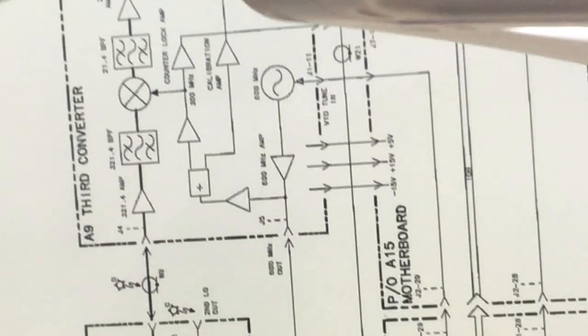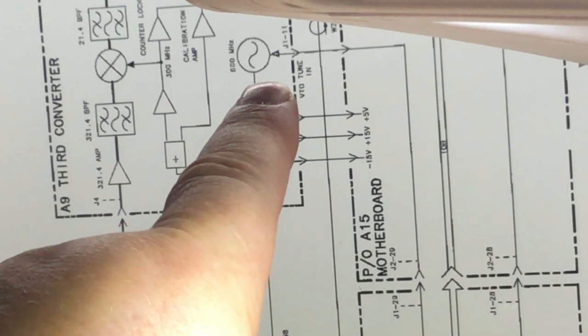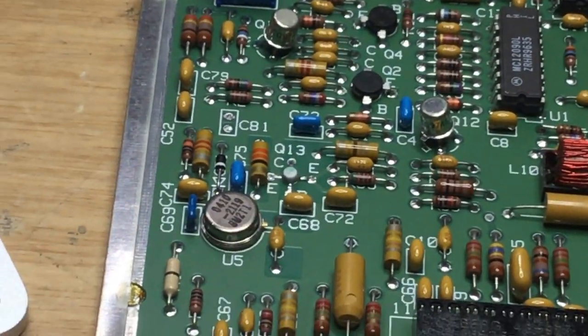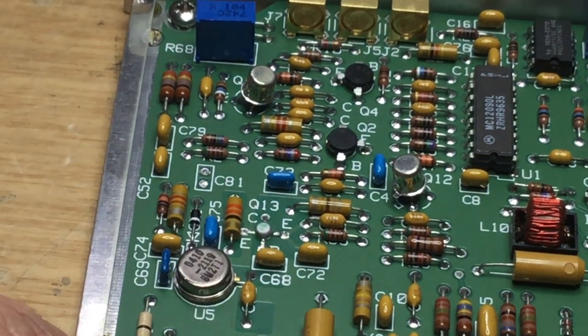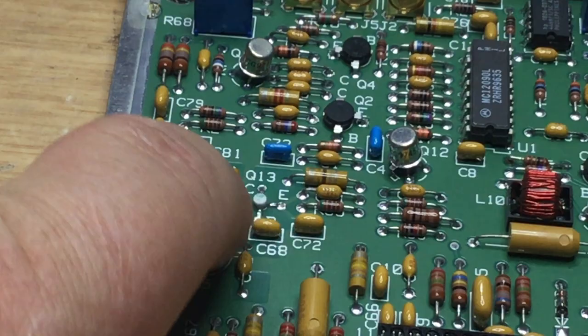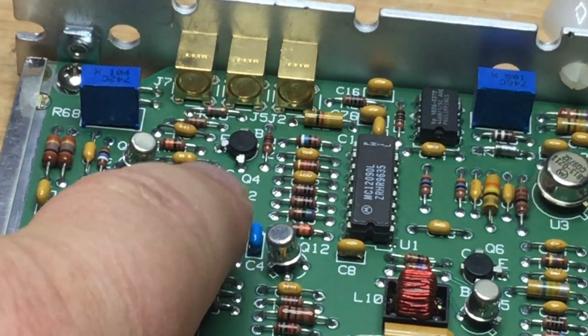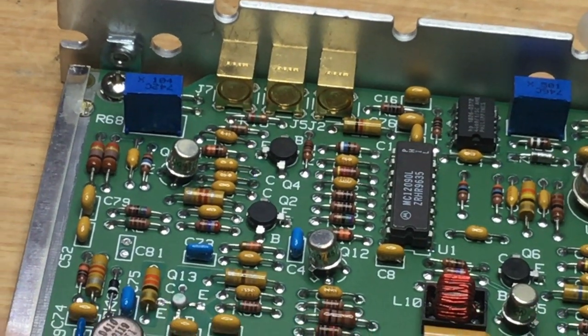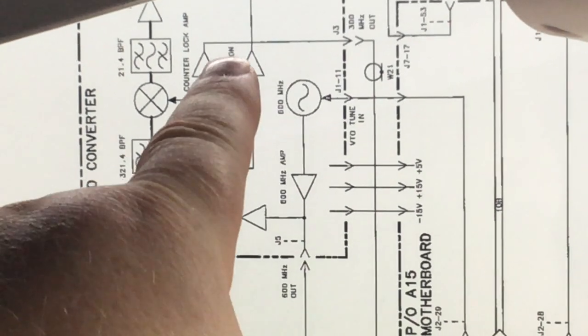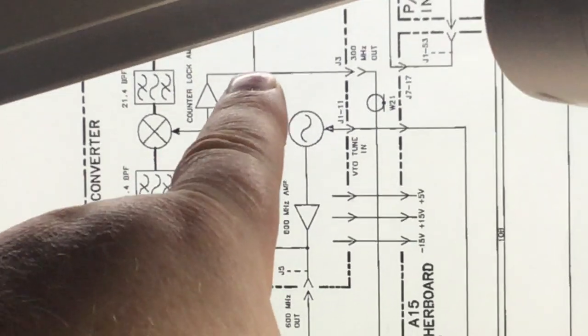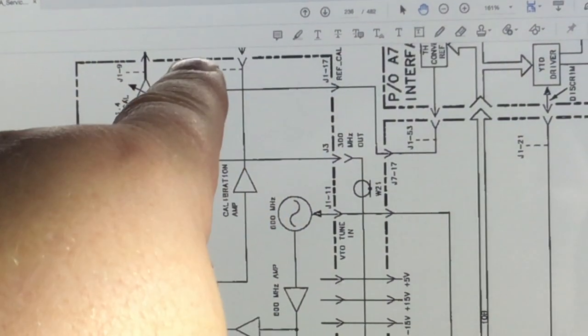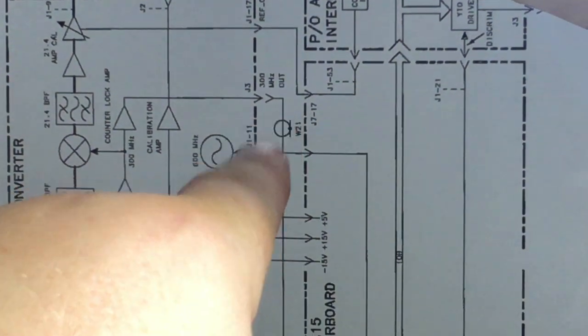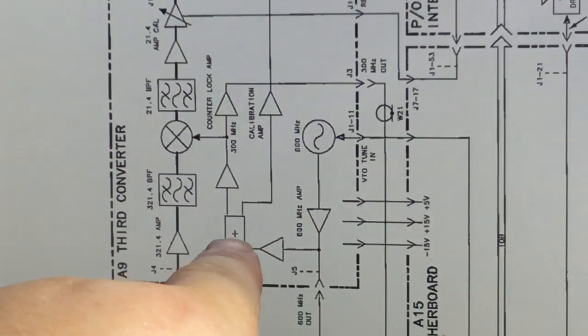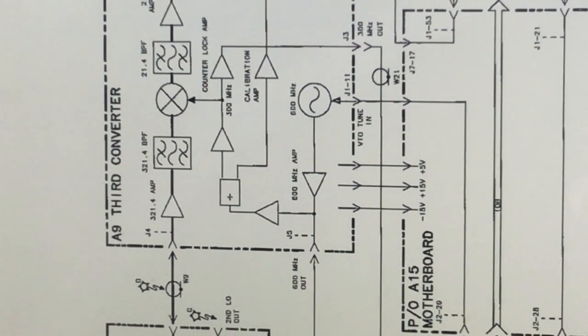Looking at the diagram a bit closer, which we can see here, I think the 600 megahertz oscillator is actually this varactor diode and that Q13. I think these two devices here, because of the symmetry and the way they're aligned on this board, are probably buffer amplifiers. One's feeding the 300 megahertz signal out to the calibrator, and the other feeds a signal back to what is a phase comparator in the other module. So I think those two devices are potentially buffers.